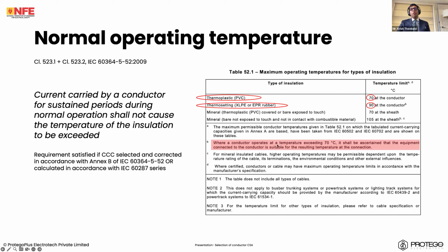And of course, where a conductor operates at a temperature exceeding 70 degrees Celsius, it needs to be ascertained that the equipment connected to the conductor is suitable for this resulting temperature. So, it's very popular to use thermosetting cable nowadays, cables with thermosetting insulation, especially for their fire performance and the amount of smoke they emit.